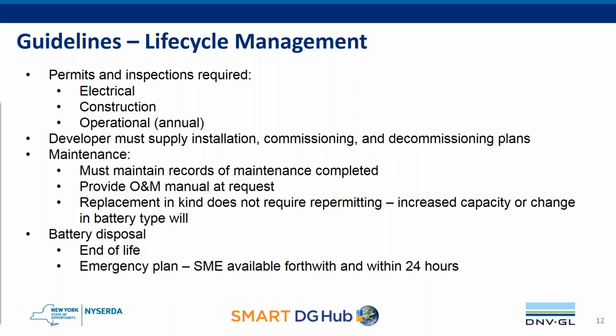You have to provide an O&M manual at request, and that if you do replacements, there won't be a requirement necessarily for re-permitting. If you are planning to increase capacity or change the battery type, that would require re-permitting and would not be considered replacement in kind. Replacement in kind would be something like swapping out a failed fuse, for instance, or an inverter of the exact same type.